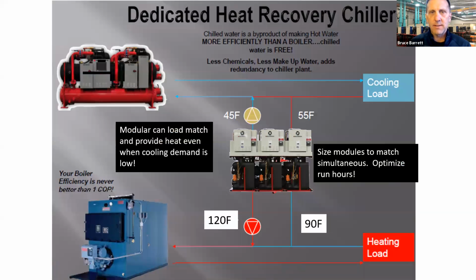And this is how it looks, some very simple piping. We take some return water going back to the chiller, and we pass it through a heat recovery chiller side stream series application. We create chilled water and we mix it back to the main chiller plant. We're extracting heat out of that chilled water return pipe. We're adding the heat of compression. We're doing the same piping on the return back to the boiler. We're intercepting some of that, taking some of that water. We're adding the heat that we just pulled out of the chilled water side. We're adding the heat of compression. We're elevating that. We're mixing water back to the boiler.